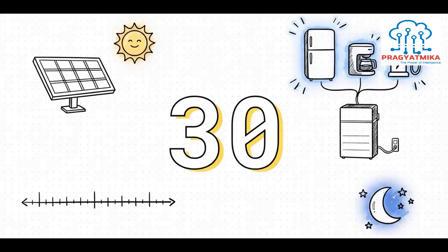You can't just guess with flat wattages. You have to accurately define that daily load by using a 30-minute interval profiling technique. By mapping out exactly when appliances are running in 30-minute chunks, you get a clear picture of the day-to-night split. The energy used during the day? Well, your solar panels can usually handle that directly. But everything running at night requires very precise battery sizing.